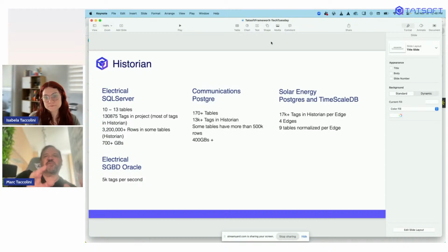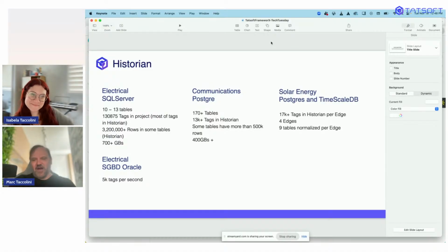So do you have 50 tags in one group, or 50 independent tags with their own sampling rate? Then, what are your sampling rates? Are you saving all tags by exception, or are you grouping some tags to save only on one specific event, like a batch start or an alarm? There are so many variables that, sorry, it's not possible to give one magic number.